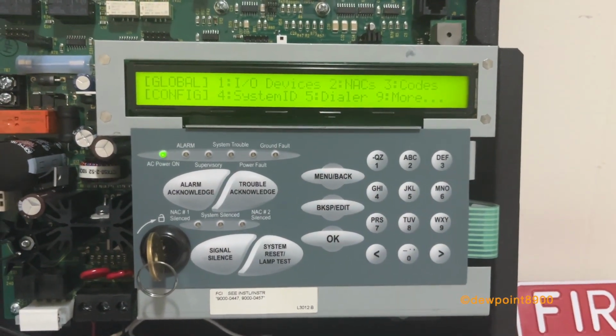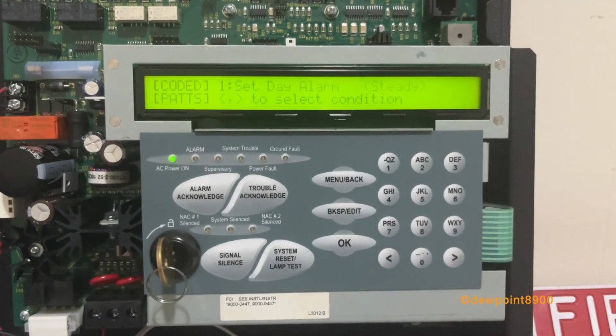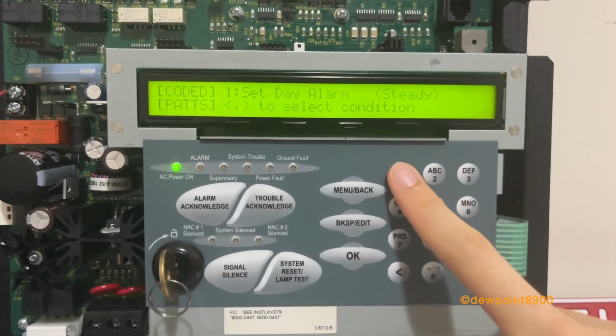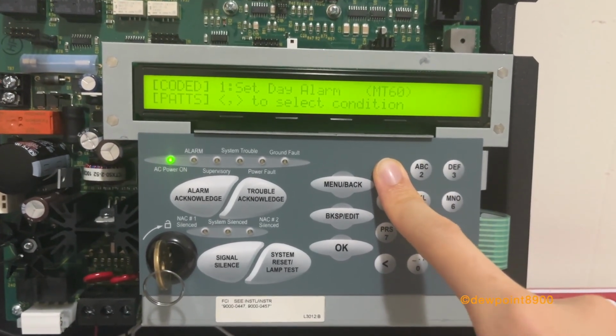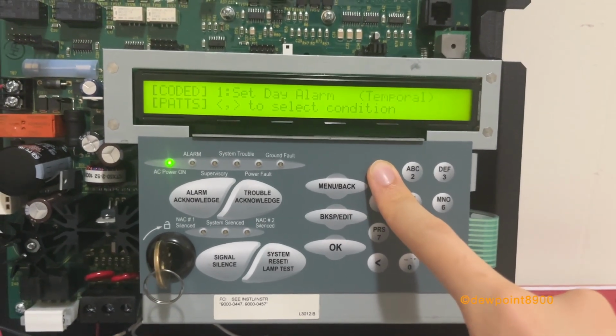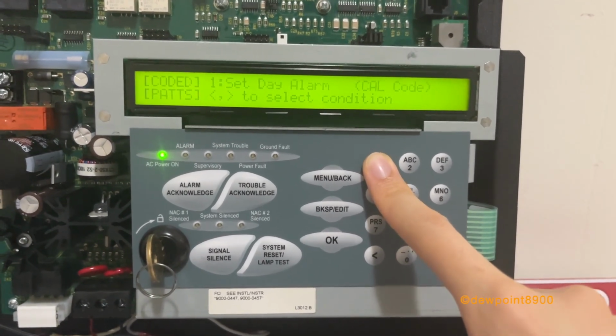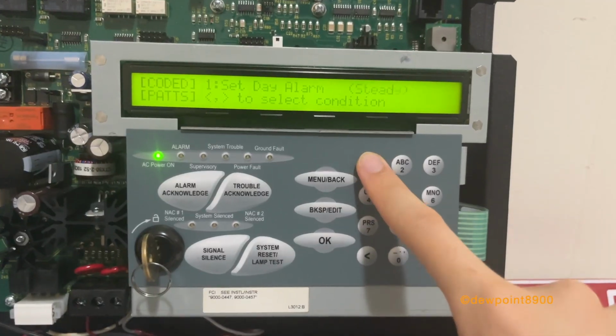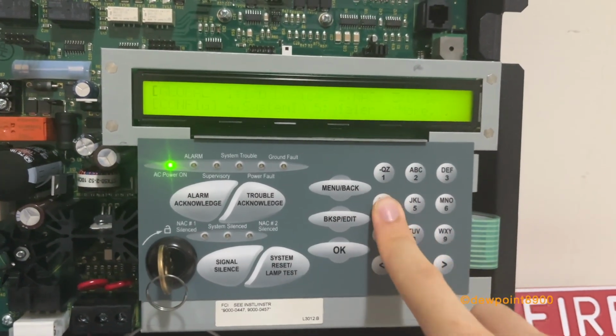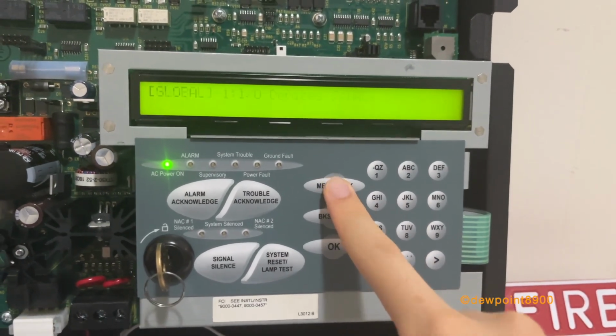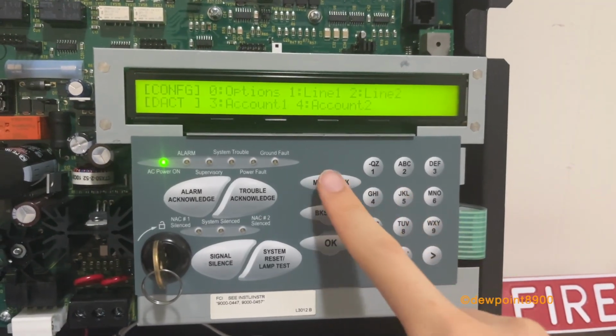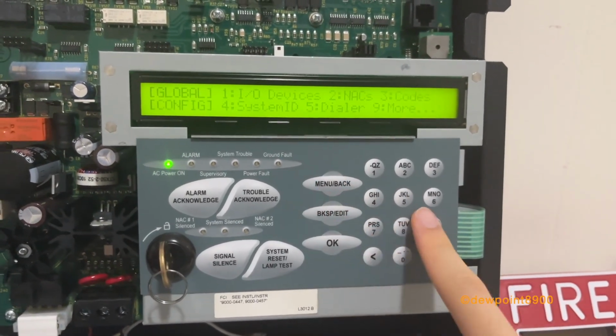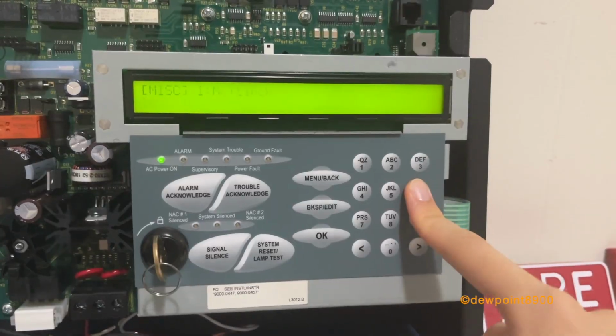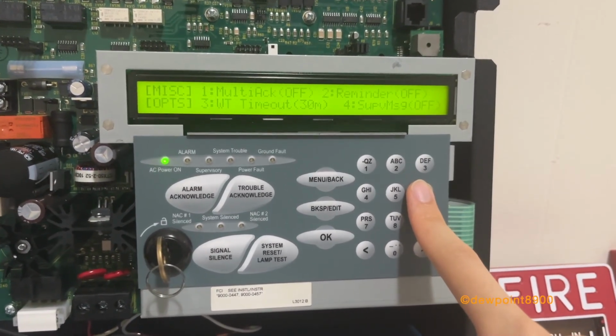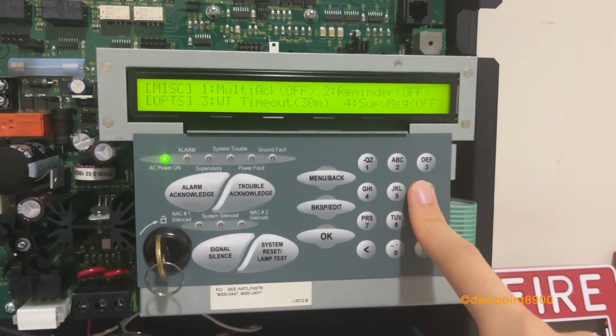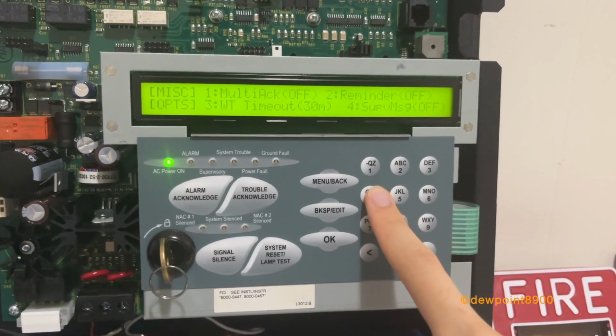The actual signal codings can be set in three codes. You set them here. You get steady, march time 60, march time 120, temporal, California code, and coded fours. System ID just sets the system normal message for the panel. Five are dialer options if one is installed. MISC options set multi-acknowledge, alarm trouble reminder, walk test timeout, and then RS-232 terminal supervision.